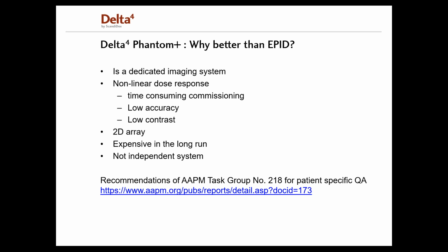Although the investment cost might be low since the EPID is usually included in a purchase of a LINAC machine, the EPID will be expensive in the long run since it is not made for exposure of high doses routinely. Using it for dosimetry measurements will shorten its lifetime and therefore increase the costs in the long run. Since the EPID system is delivered by the same vendor as the LINAC itself and is part of the LINAC, it is not an independent system. Last but not least, according to the TG 218, it is recommended to do patient-specific QA with a stationary measurement device system placed on the treatment couch.